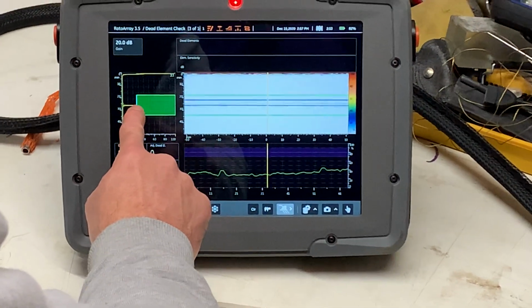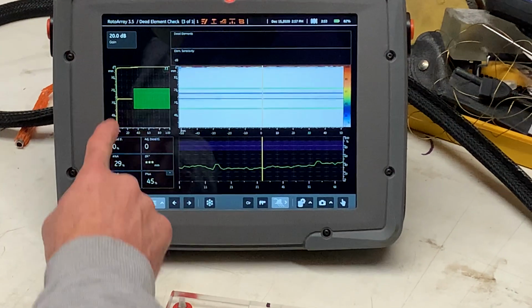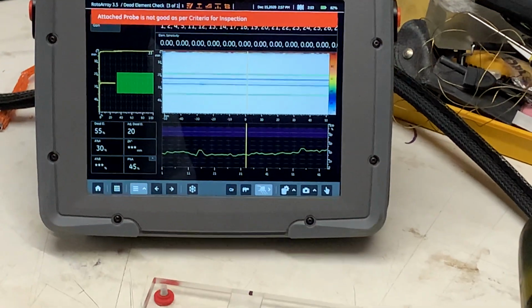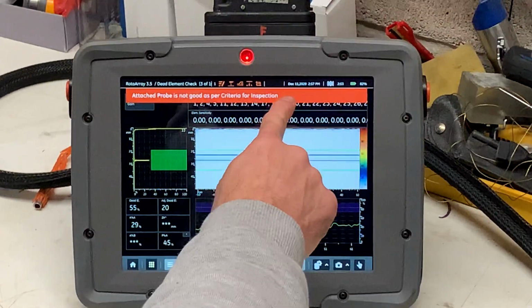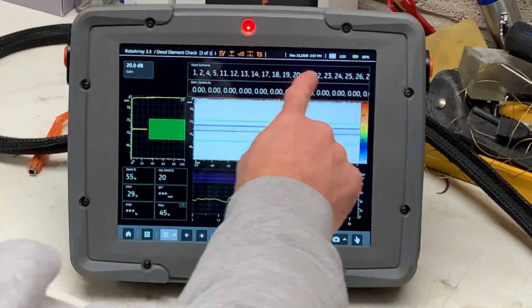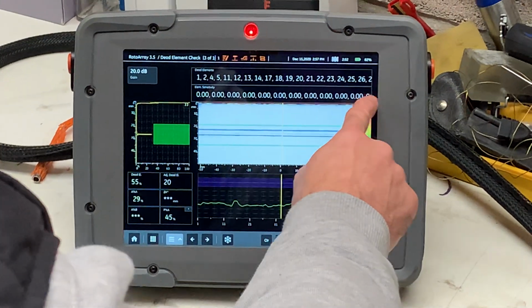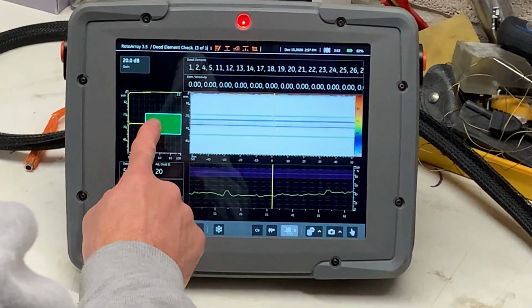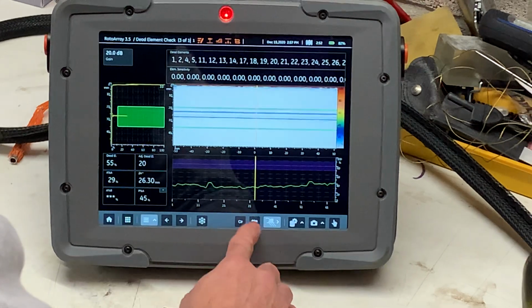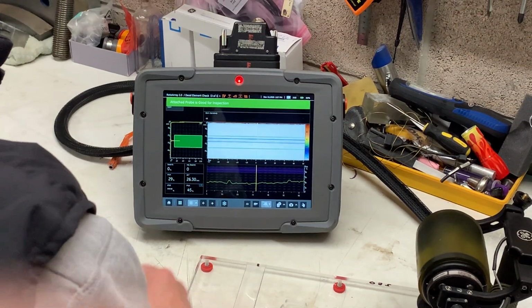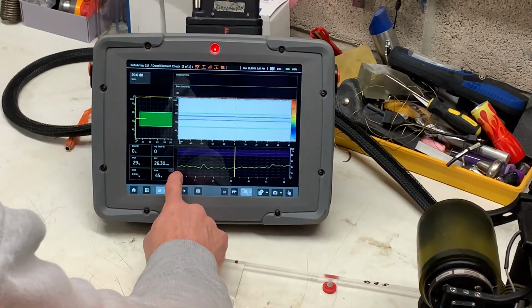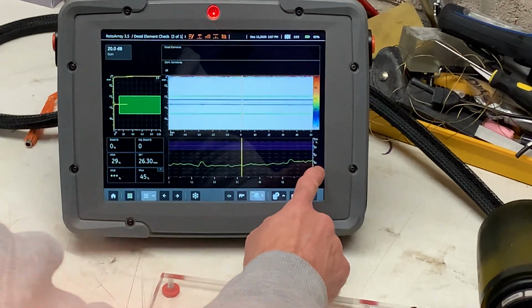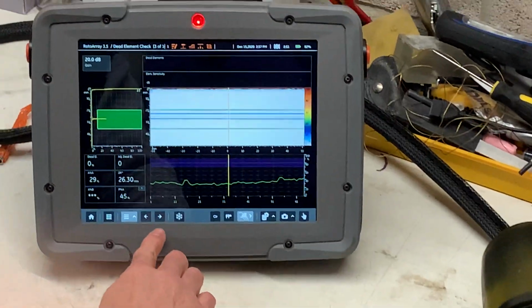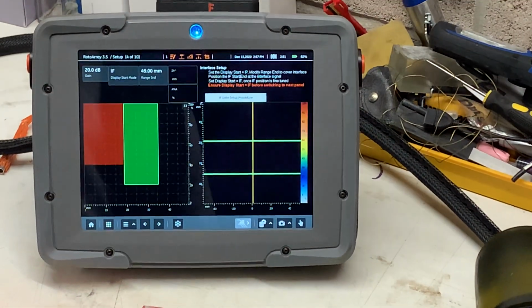So I'm just going to fake now that some of these have failed by moving them out of the gate. Hit the calibrate again. Now we get this red message, and it tells us which elements are dead and the loss of sensitivity. So let's just put that back before we carry on. Hit that. So obviously you can see by the output of each element that they're all firing. So that's what we need. And we use the arrow again to move to the next step.